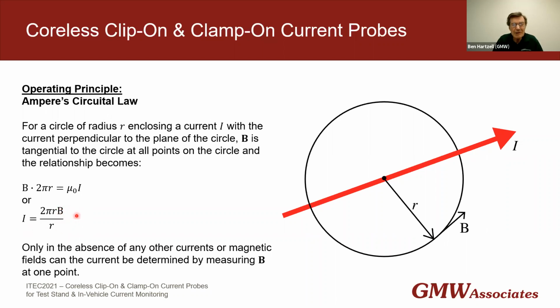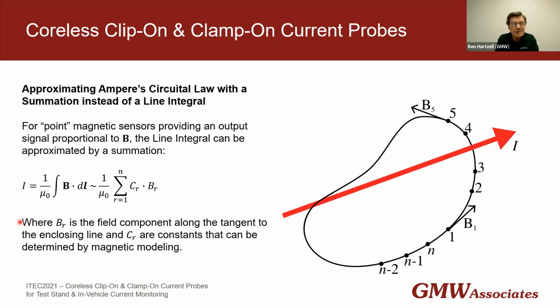The only problem is that if this B has other field contributions from external currents or steel plates or the environment, then you don't get a correct value of I. So what we have done is make a summation approximation of Ampere's Circuital Law. We've located sensors that are sensitive to the field along the tangent to the line. So we measure the amplitude B at point 1, point 2, point 3, point 4, etc.